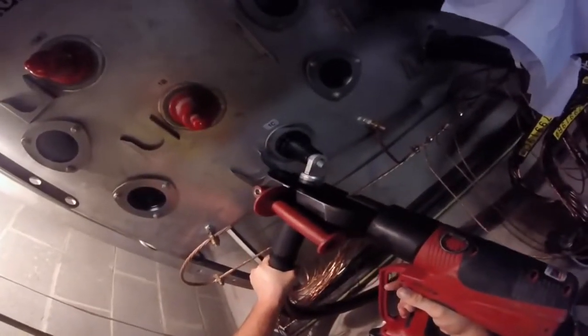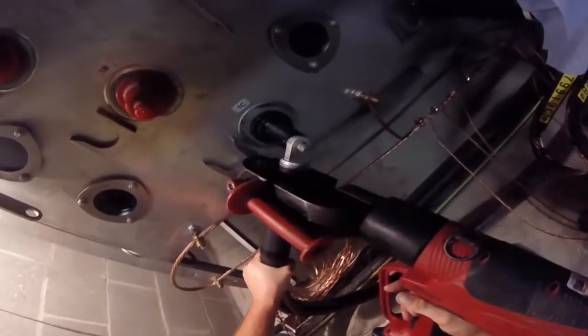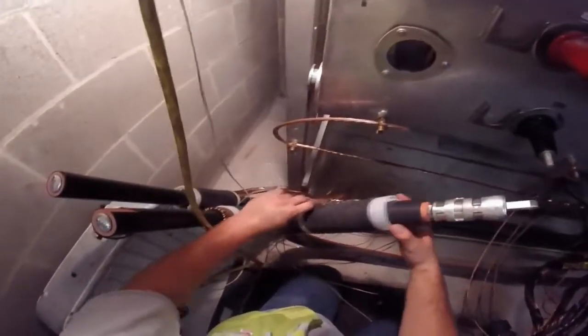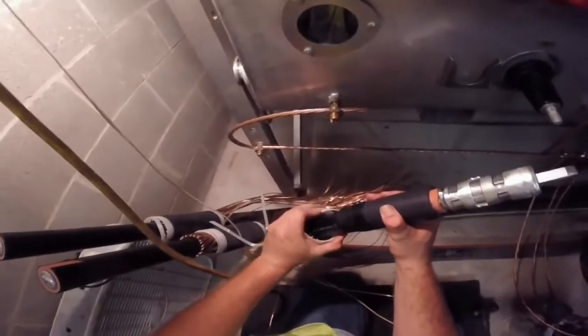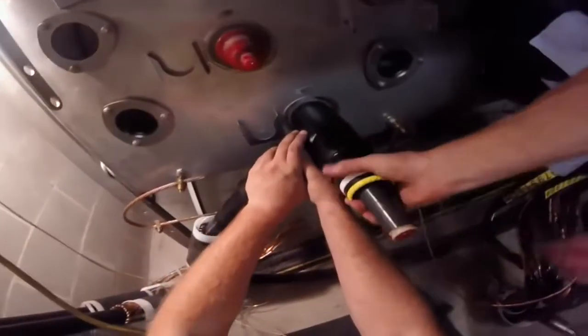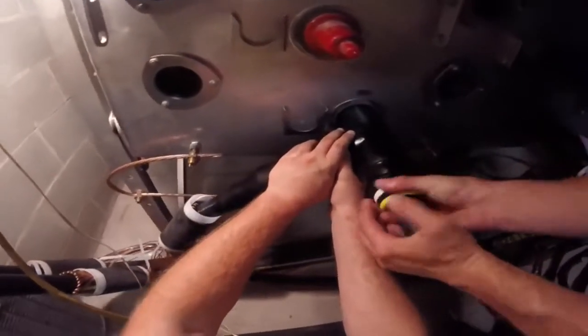First he's going to go back and make sure he's got the right distance between the cable and the connector on the switch. With that secured, he's going to finish his crimps. Then he puts the cold shrink termination back on before making the connection. Notice those clean crimps in various directions. Now a little more lube to make sure the T-connector connects up to the switch quite well. He slides that in, then slides the cap into that and tightens it down.